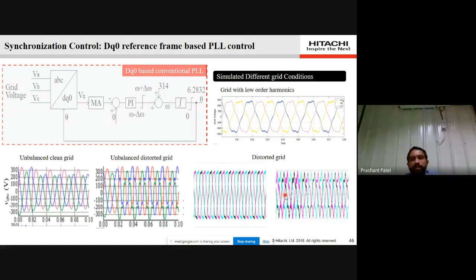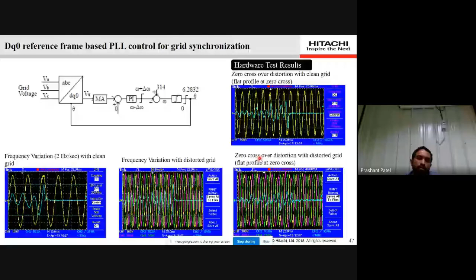Here you can see as soon as we applied the step load, the converter fails with a zero crossover distorted grid. With a frequency variation of 2 hertz per second, this PLL is unable to maintain synchronism. With a frequency variation and a distorted grid also, the converter loses its synchronism. Again, with a zero crossover distorted grid and a frequency variation, the converter was unable to maintain synchronism. So these are the issues of this conventional PLL: it loses its synchronism, it fails to operate with zero crossover distortion, and many industrial grids often have zero crossover distortion, and the dynamic response is also slow. So we have to think about another synchronization control.